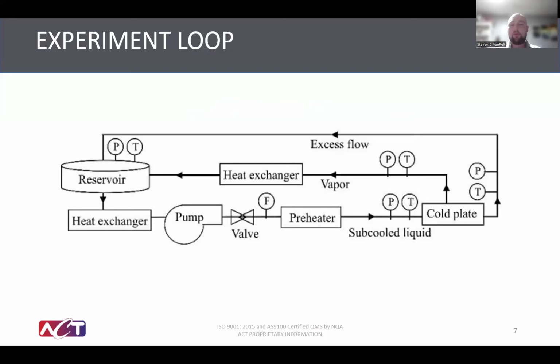Once it's in the reservoir, it's ready to be called upon, and we can pull it through this system, pump it up to whatever pressure we need, and then it goes through this preheater. This preheater is a very important part of the design because it allows us to control the inlet temperature at the cold plate. For our testing, we maintained it from 13.2 to 13.8 degrees C.